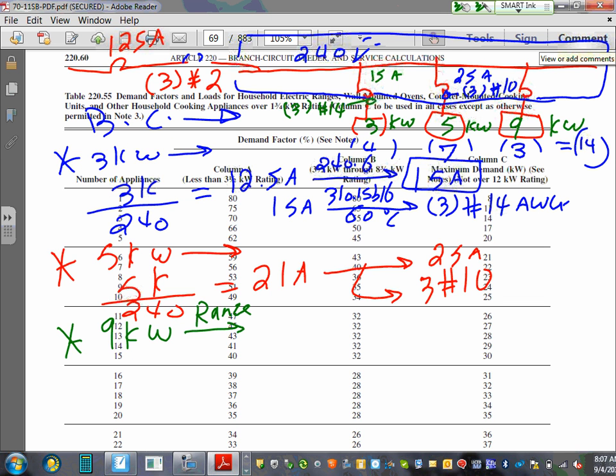They allow you to use the table. For a range, they allow you to use the table for branch circuits. Only for range, not ovens, not counter-mounted cooking units, only for range. And by the way, all the stuff that I told you, all these rules are right at the bottom of the table. Can I get you guys to understand, for a range, you are allowed to use the table. Okay, so for one range as a branch circuit from this table. Here's one range, and this range is under column C, right? So what's the demand for it? Can you guys see it here, right here? What is it? 8. So 8 kW.